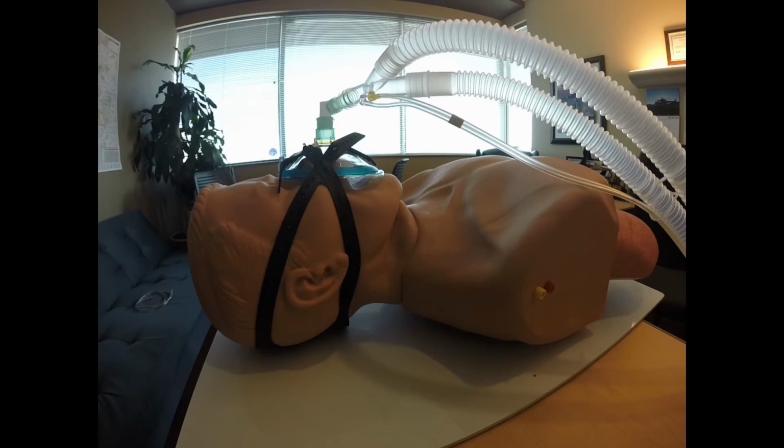It is important to note that a good mask seal with the patient's face should be achieved. Excessive leakage will adversely affect exhaled volume measurement accuracy. Minor movement in the patient will increase those leaks. One of the things that you can do to help alleviate some leaks is to increase your bias flow.